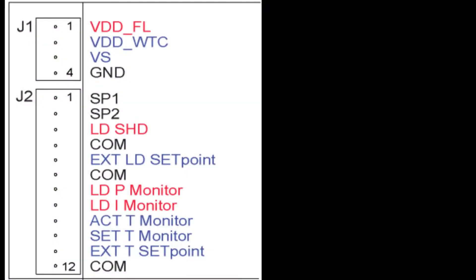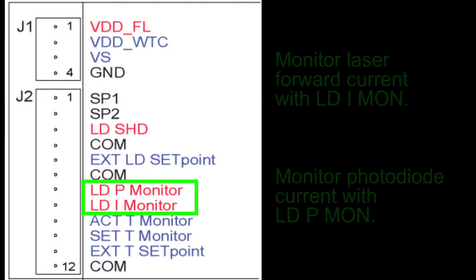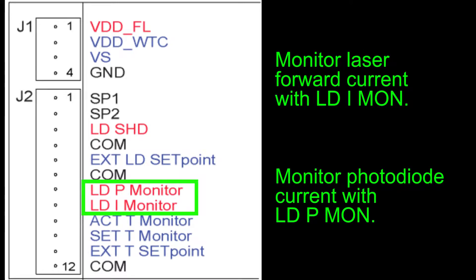There are monitors for laser forward current and photodiode current. Both monitor signals are available at all times, regardless of whether the driver is operating in constant current or constant power mode.